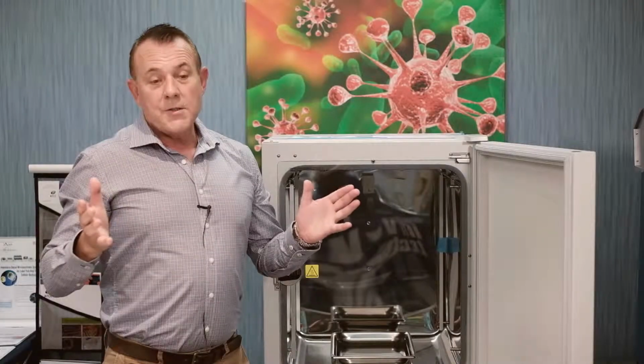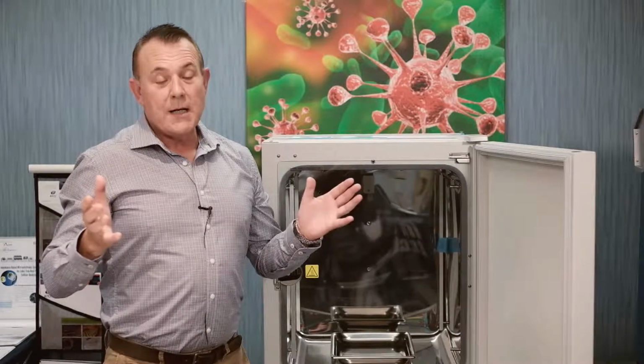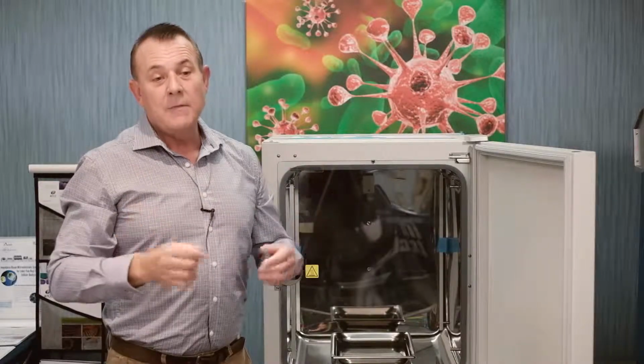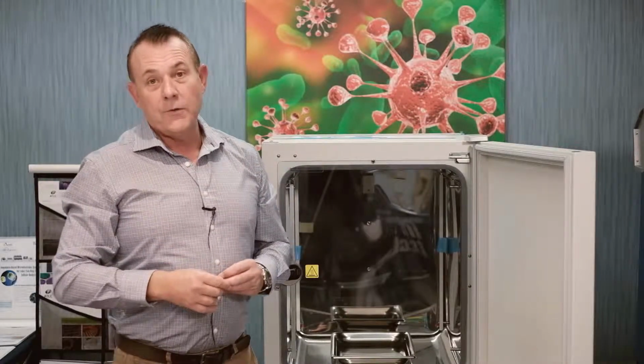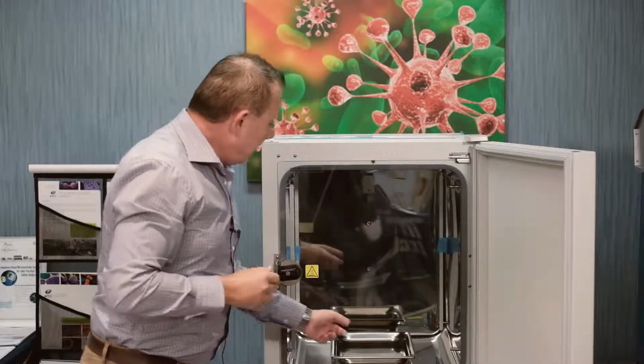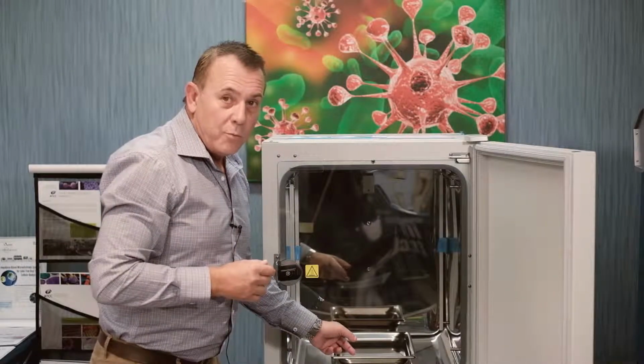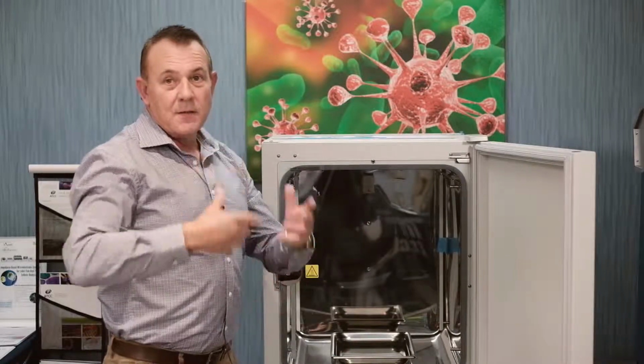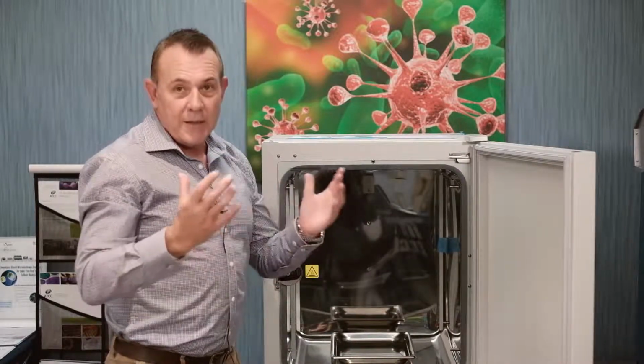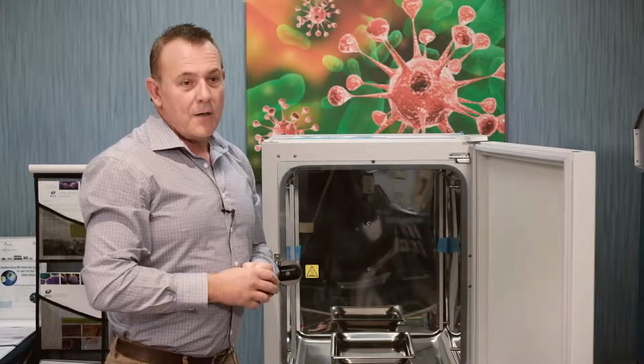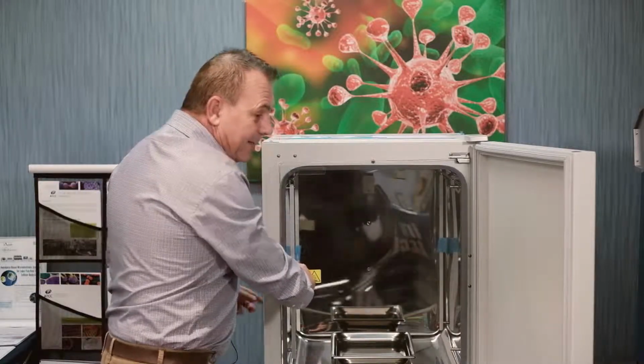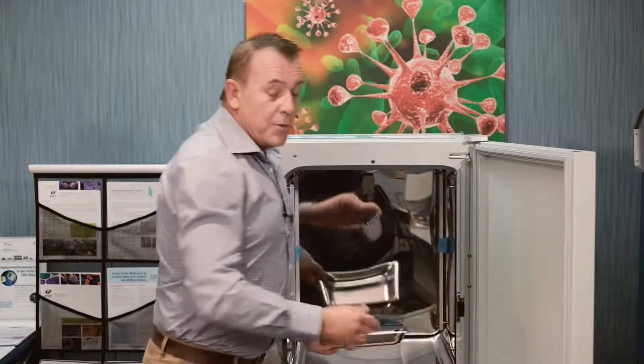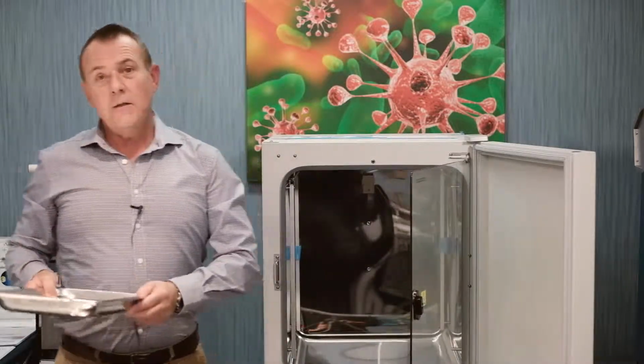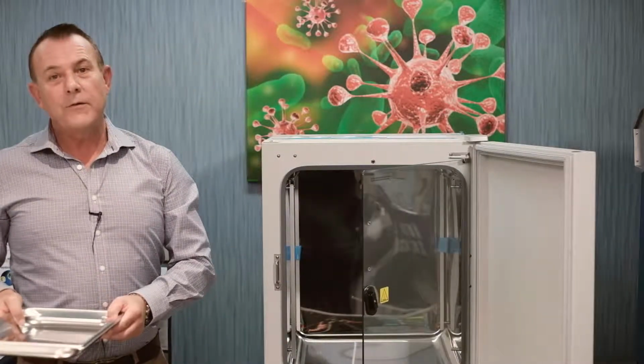The dual sterilization ranges are 95 degrees C and 145 degrees C. At 95 degrees it's a moist heat, so we leave the water pan in with water, giving us the condensation or humidity to sterilize. If we want a dry heat sterilization mode, we take the water pan and water out.